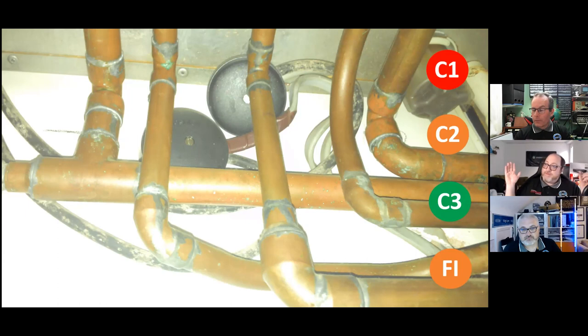So again, FI for me, and I'd be in there like a hawk. And probably my FI might end up just moving it out of the way anyway. I don't know. You probably would just remove them away from the pipework, put them in some sort of fixed base connectors. There is this problem, obviously, where we have this wiring system, because you've got the twin cores there, and are those flexes coming out to the... so it's part of the central heating wiring, I guess. Yes, so it is. Ownership of responsibility there.